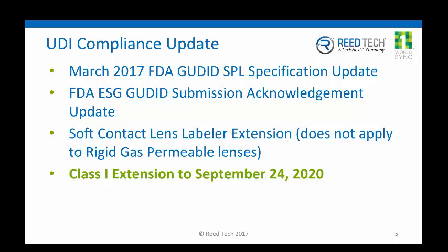And lastly is the third acknowledgement, which I believe folks in the business really eagerly await, because that includes the results of your submission. In a perfect world, it just simply comes back with your device identifier that says you've passed. So great, you've met the FDA's request. However, it also includes some error messages if you have any issues.